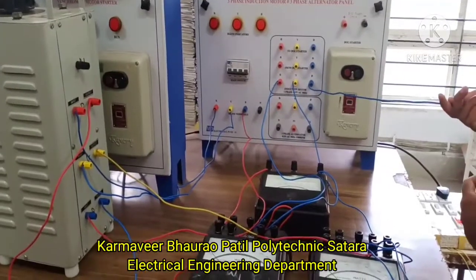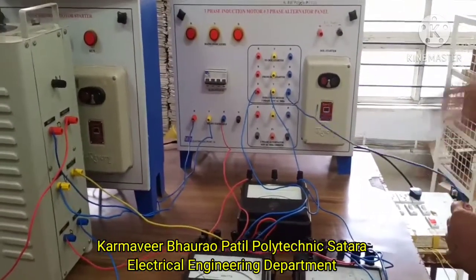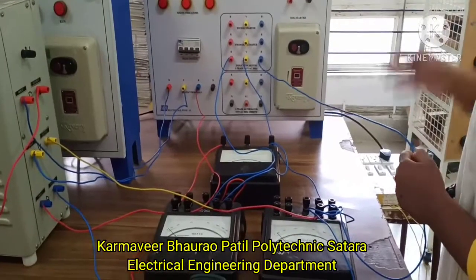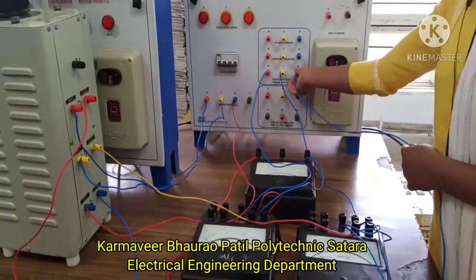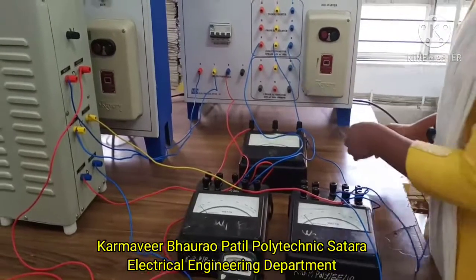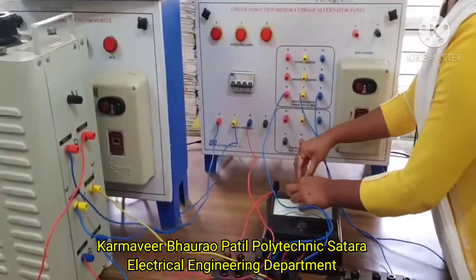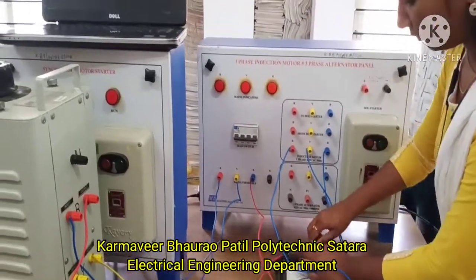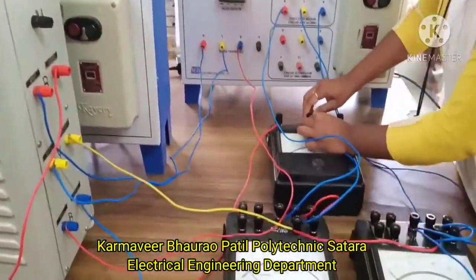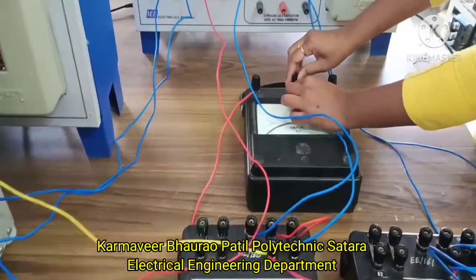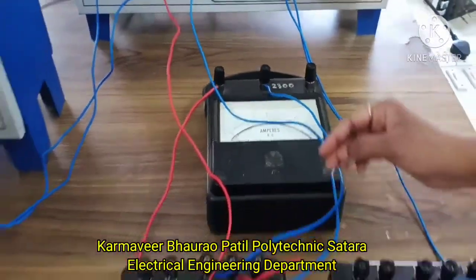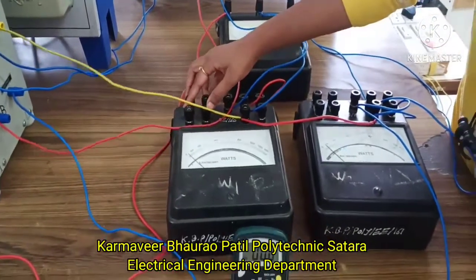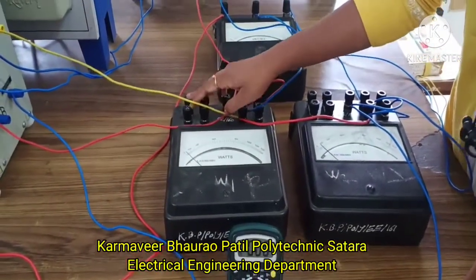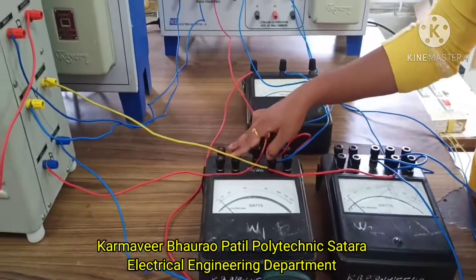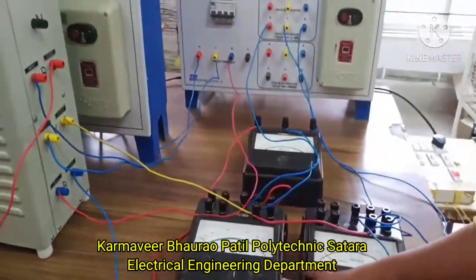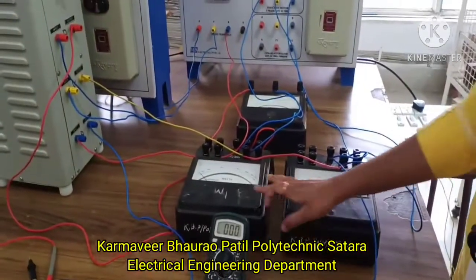Now we will perform the block rotor test, and as we get high current for the block rotor test, we are connecting this ammeter to the 10 ampere range. As we are getting high short circuit current, we are selecting the 10 ampere current range. And we will also connect the wattmeters' connections in parallel, so that we get the 10 ampere range for both wattmeters W1 and W2.